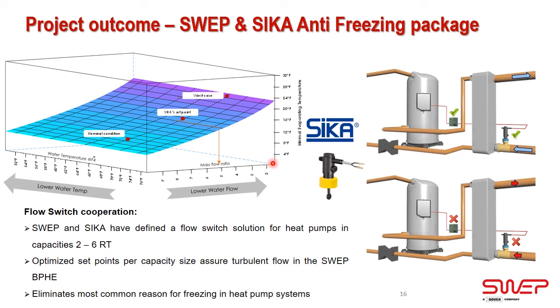So what SWEP and SIKA did in cooperation was that SWEP defined the flow levels that we thought were adequate for turbulent flow and not to limit the operating envelope of the system. And SIKA developed a flow switch range that is color coded for the different capacities between 2 and 6 tons. So for each tonnage of heat pump, it's possible to find the SIKA flow switch that will stop the compressor if the ratio goes below about 1.5, which is about half the nominal flow of 3 GPM per ton, which is the industry standard flow range.